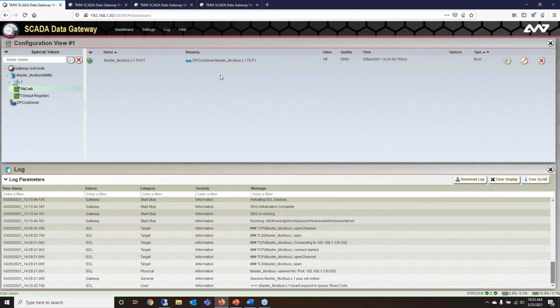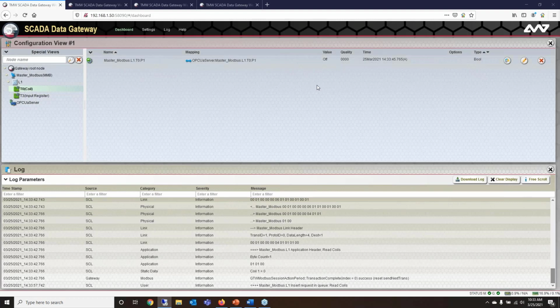So now when I go back to my coil, my data type is still in here. And what we'll see is if I go ahead and change the data in my DTM, after that 15-second polling period, we should see the value inside of our gateway update. So we'll just give it a little bit more time. And sure enough, it did. So now I'm able to change the value inside of my Modbus server, and we'll have that information inside of the gateway. Now, it doesn't have to be simulated like we're doing in DTM. This could actually be a physical device, a simulated device, anything along those lines, as long as it's communicating across this Modbus protocol. So now we have access to roughly 15 seconds of difference, real-time information.